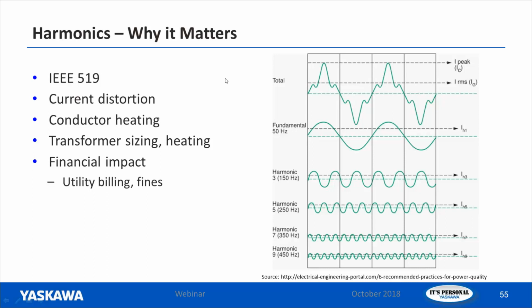So that's why harmonic distortion can be a problem. So why does it matter? In many cases, it's going to matter to you because you need to meet IEEE 519. Current distortion results in conductor heating. It'll affect the sizing of transformers. If you've got your transformers sized properly, but you don't account for harmonic distortion, or you didn't know you were going to have it, now you're going to have transformers overheating. You could have larger utility bills and then possibly even fines.